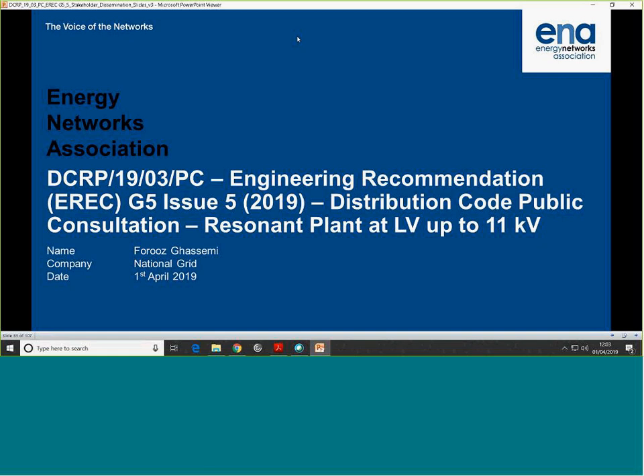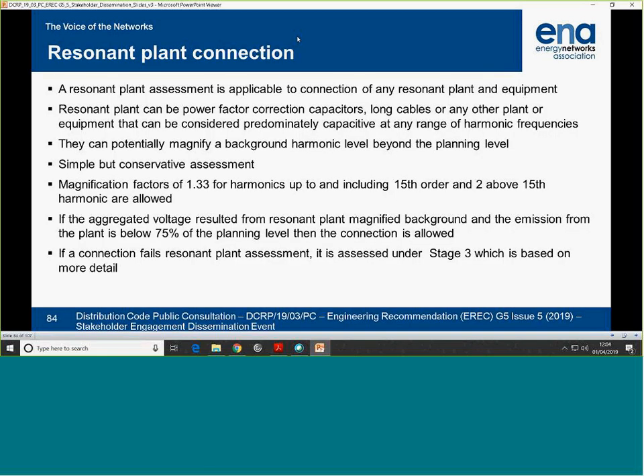So we thought we need to give conservative guidance to people, and if they fail that stage, then they have to assess it in a more rigorous way, like a stage 3. So it applies to cables, capacitor banks, converters with apparent capacitive impedance. And active front ends may behave that way. At certain frequencies, it may show negative reactance. So it's a quick and conservative assessment.